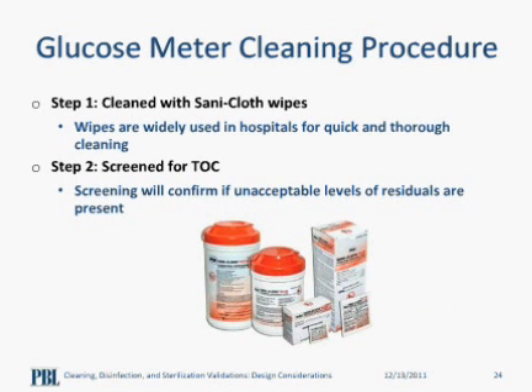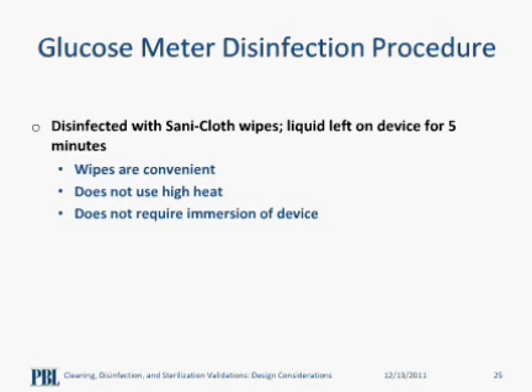So what we did with this meter was clean it with wipes, which are widely used in hospitals. We screened it for TOC to confirm that the cleaning will remove unacceptable levels of residuals that may be trapped in crevices or buttons of the device. Then we disinfected the device with the same wipes, only this time we left the device wet with the wipes for 5 minutes. This renders the device disinfected without the use of high heat. And the use of wipes was also convenient and did not require immersion of the device.